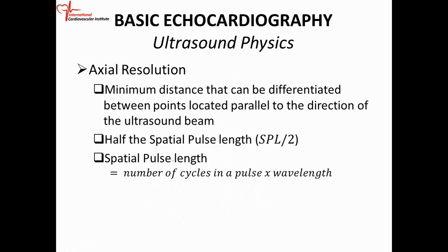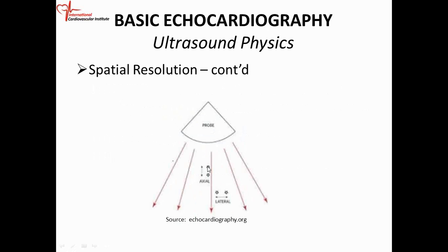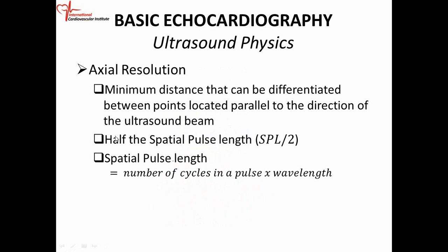All right, so axial resolution is the minimum distance that can be differentiated between two points located parallel to the direction of the ultrasound beam. With axial resolution, the ultrasound beam is parallel to the points. One point is there, the next point is there, and the beam runs in the same direction as the points. And with lateral resolution, the ultrasound beam is perpendicular to the points. So axial resolution is the minimum distance that can be differentiated between two points located parallel to the direction of the ultrasound beam.